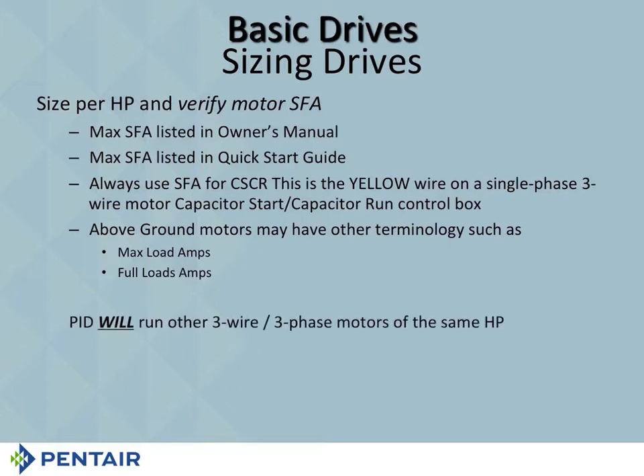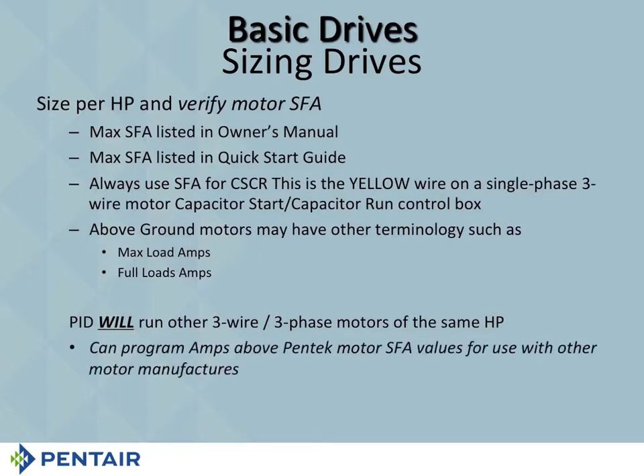Now, the PID will run other 3-wire, 3-phase motors of the same horsepower. In other words, we didn't set the drive to equal just our own service factor amps. We went out, we looked at everybody's service factor amps, and we said, okay, who's got the most? That's the one we want to use. And so any of the 3-phase motors out there, whoever had the most service factor amps, we've programmed the drive so that it could run that motor too. You still have to set it for the proper service factor amps.